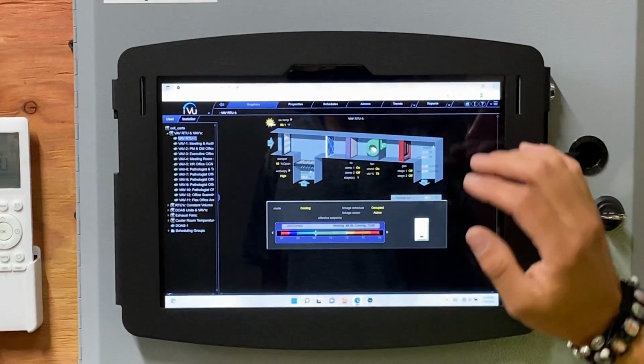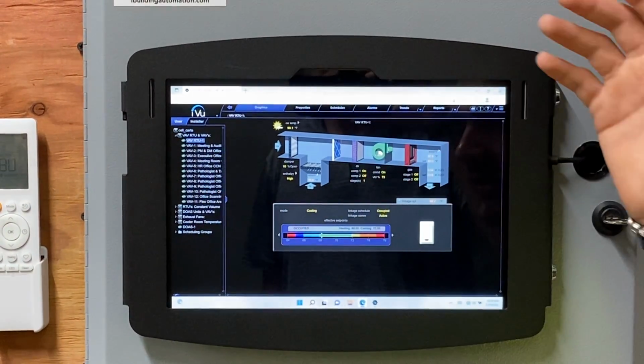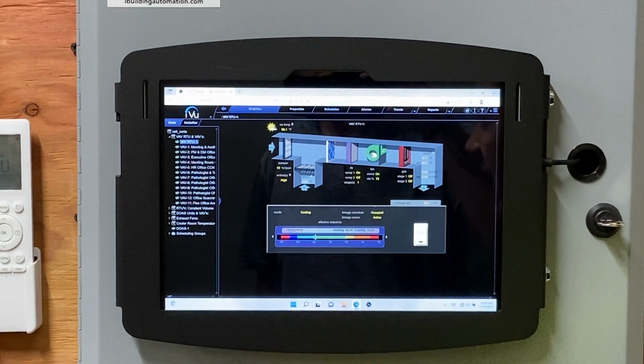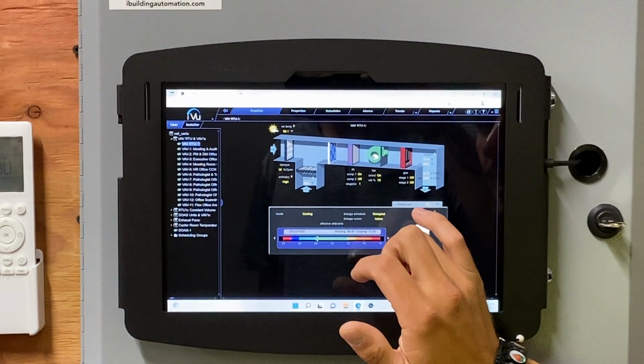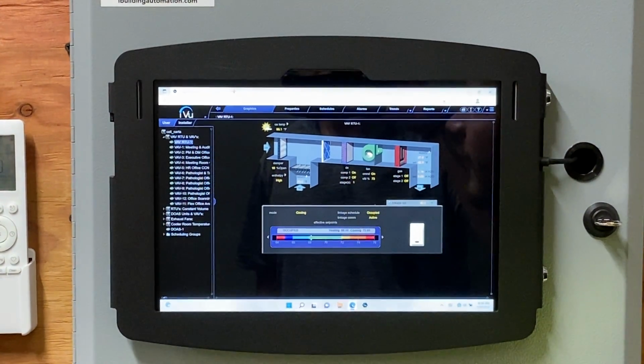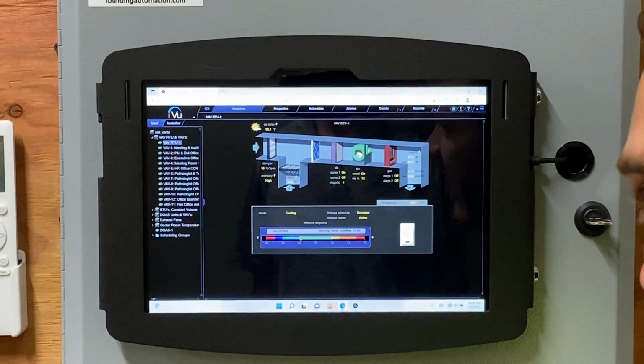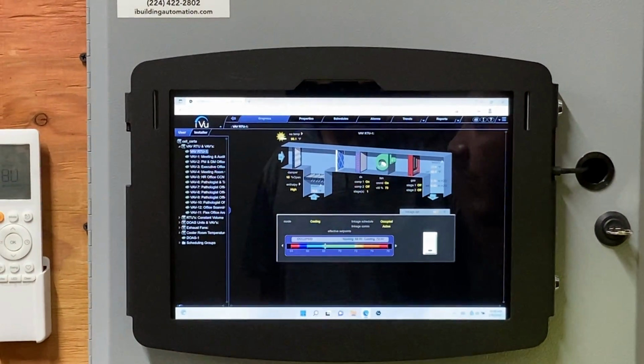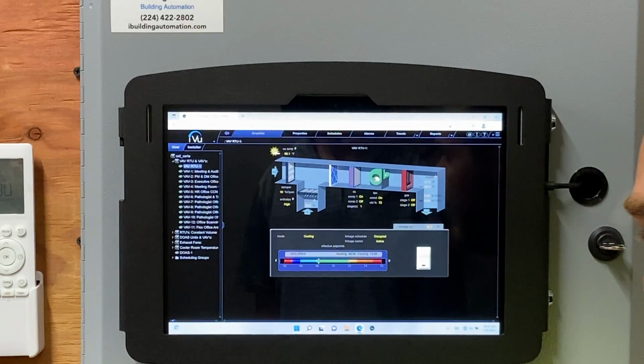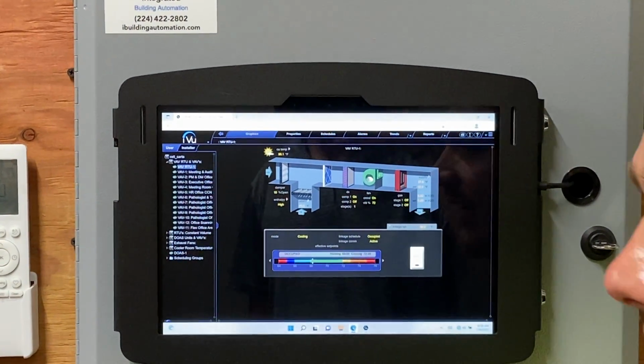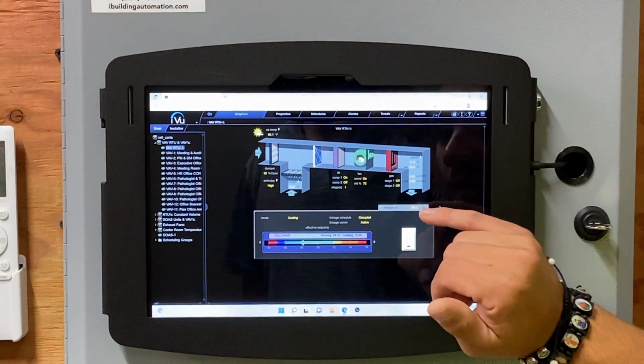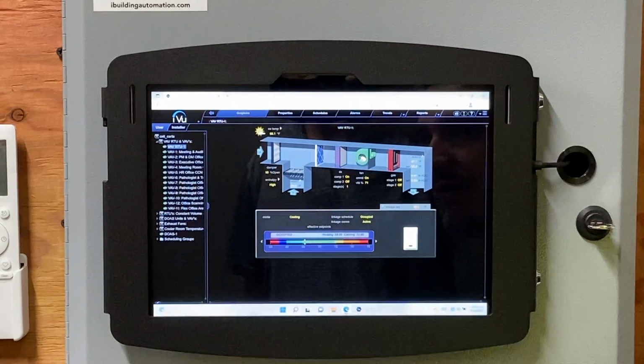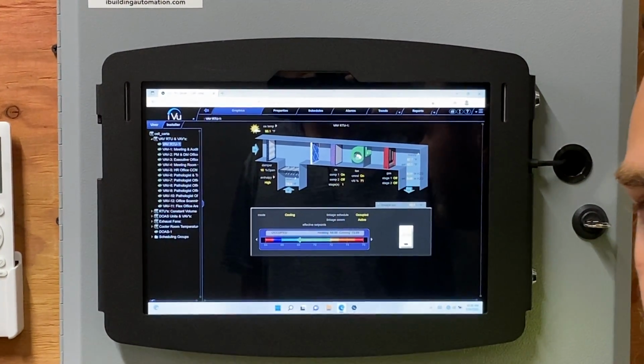This works off of a linked VAV system, with linkage VAVs. So we have our linkage set point, which is an average of all the thermostats for each of these VAVs reported back to the rooftop. That's how the rooftop is going to navigate, based on the linkage set point, which is, again, an average of all the VAVs that are on that set of links.